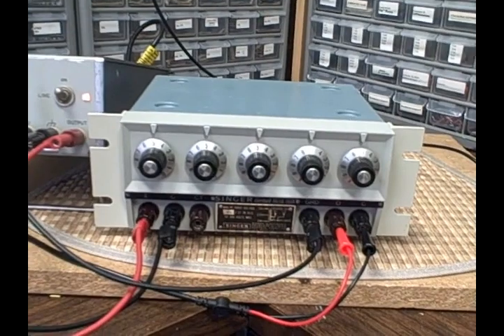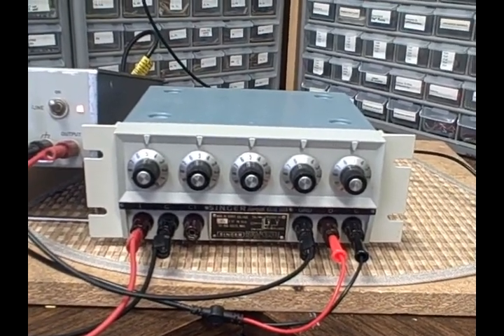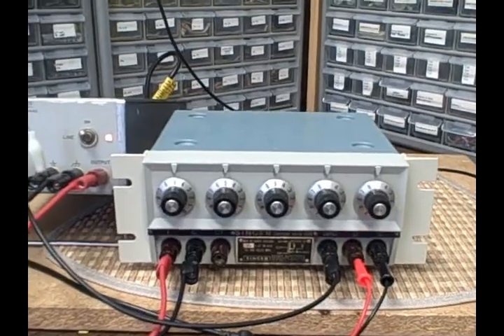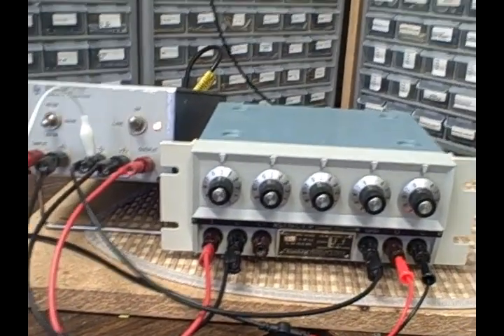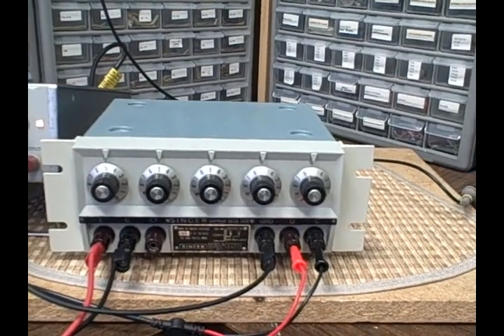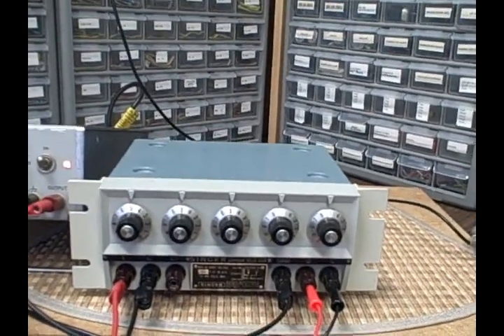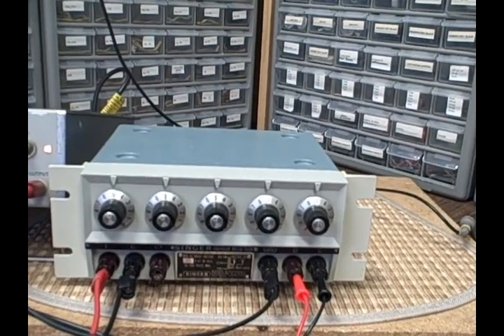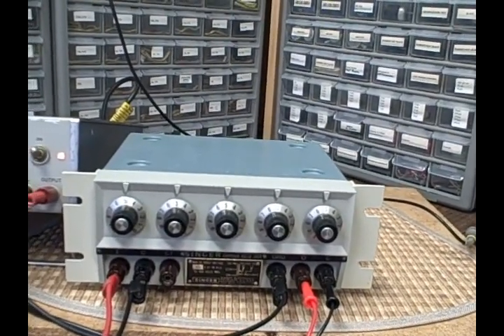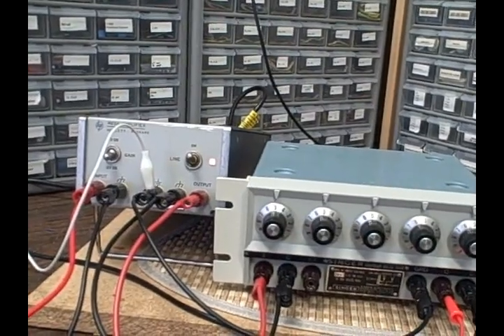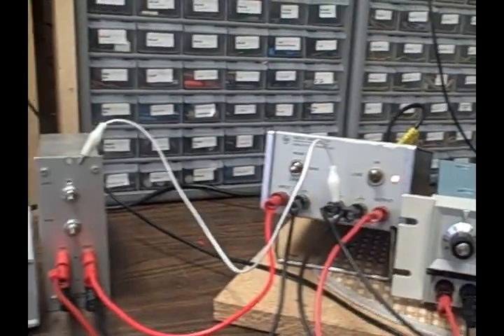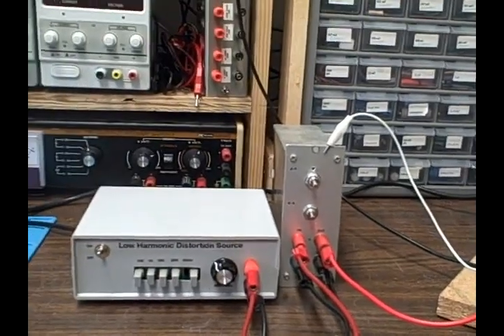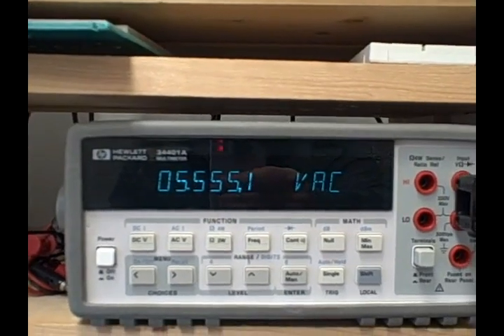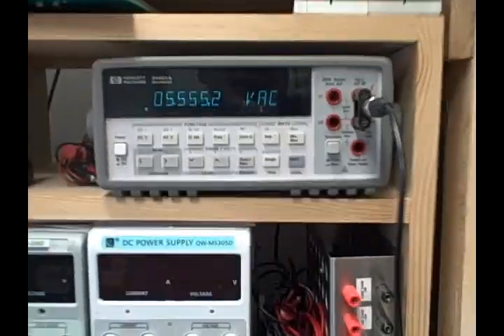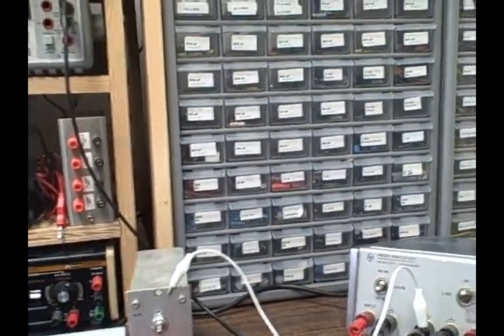The stated accuracy for these units is about 0.001%, so a thousandth of a percent. Pretty amazing precision. As long as you leave it basically unloaded, so you're using a high impedance on the output, and it doesn't load it down and create currents through the transformers, then you're going to have a very accurate output as a proportion to the input. We are still at 5.555 right now, with small fluctuations in the 10 millionths or 100 millionths place.